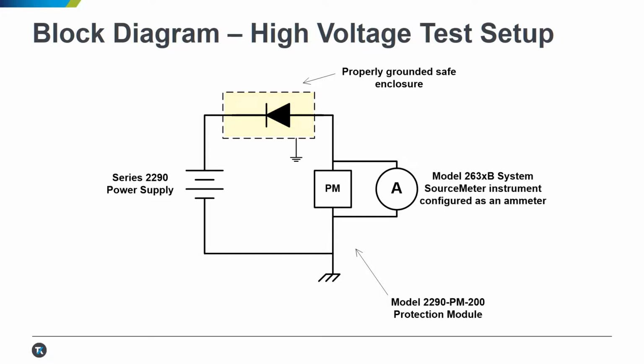The DUT should be in a safety enclosure rated for 10,000 volts. The case can either be a case with a metal enclosure, which needs to be grounded, or the case can be plastic and isolated from earth ground. In either case, a proximity switch is needed to prevent the 2290 from outputting voltage unless the top of the enclosure is closed and properly seated upon the enclosure.